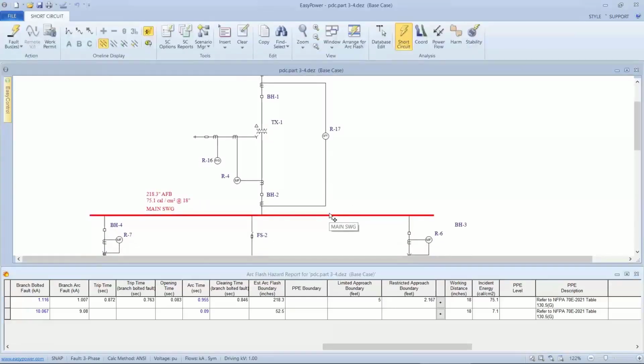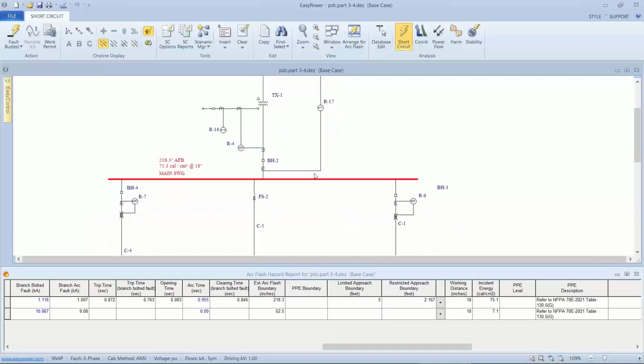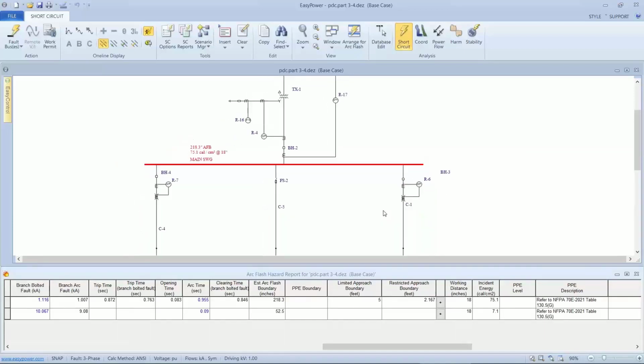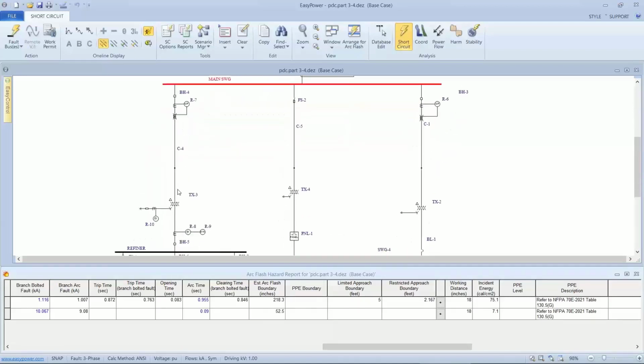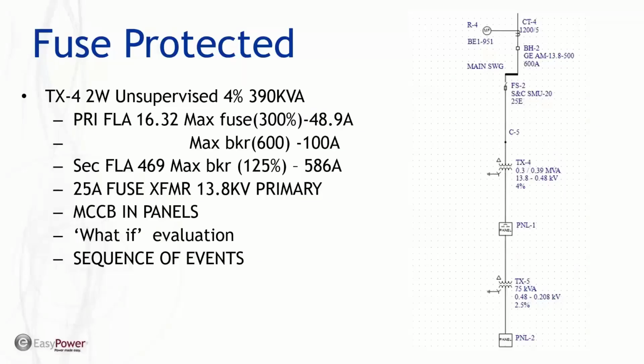Now, arc sensing is the same thing. We could have arc sensing for each of these downstream buses by putting the light sensor loops in these areas, and then predicting what the downstream protection would be based upon the manufacturer's data sheet. Okay, it looks like we're running out of time. I did want to show this.